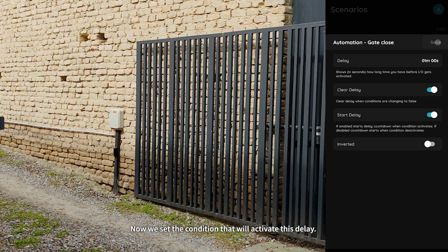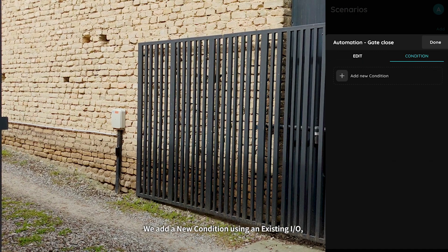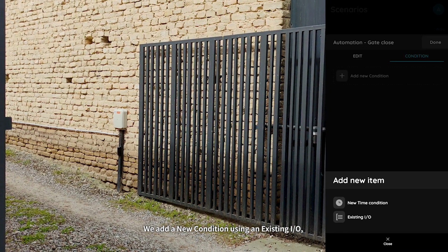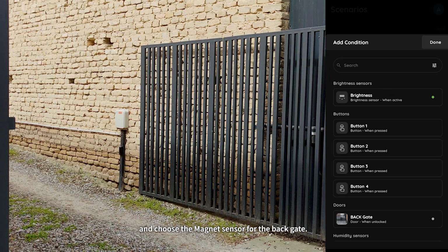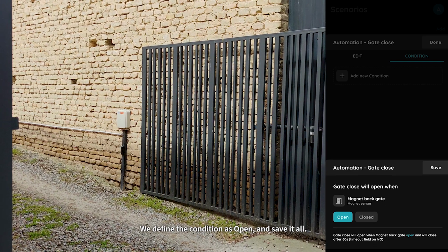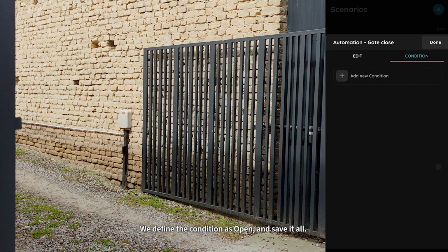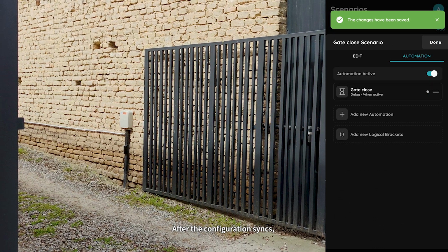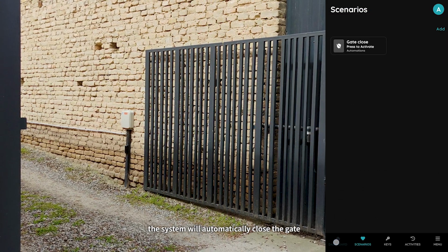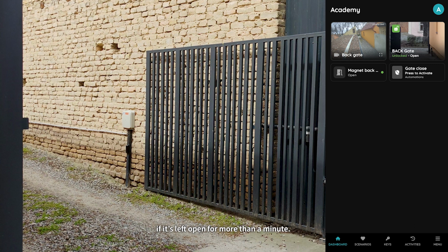Now we set the condition that will activate this delay. We add a new condition using an existing I/O and choose the magnet sensor for the back gate. We define the condition as open and save it all. After the configuration syncs, the system will automatically close the gate if it's left open for more than a minute.